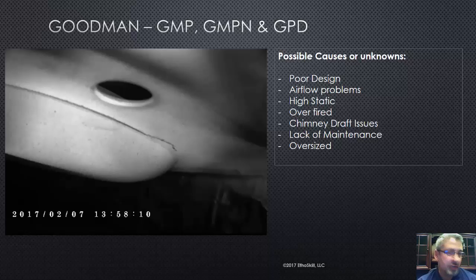Suppose this customer had chosen a new heat exchanger as a repair versus replacing the system. We go out and install a new heat exchanger, and you do a really good job installing it. But if you don't check static duct pressures, combustion analysis, or filter size, that's a problem. A lot of times the filter opening they cut is half of what it should be. So even if a furnace is replaced, as an installer you also need to check airflow and these other things, because if there's a problem with the duct system, too little return, or oversizing, you'll just install a new furnace and cause another problem.